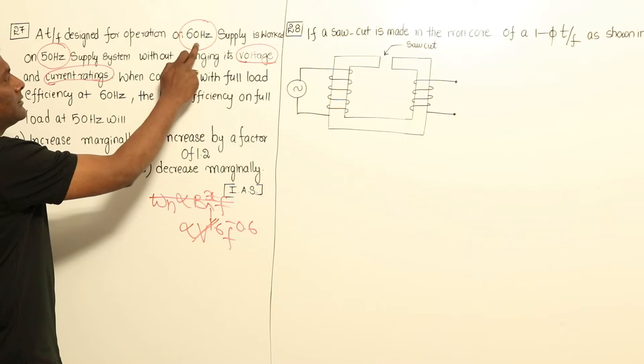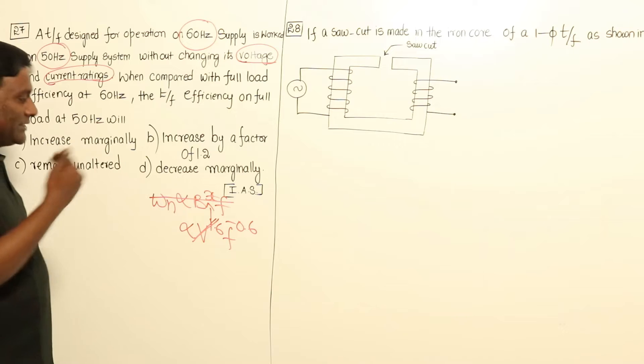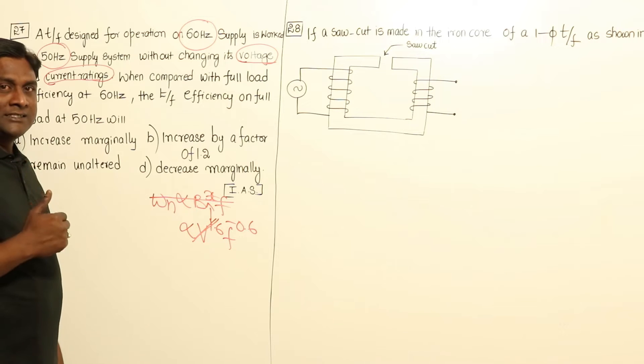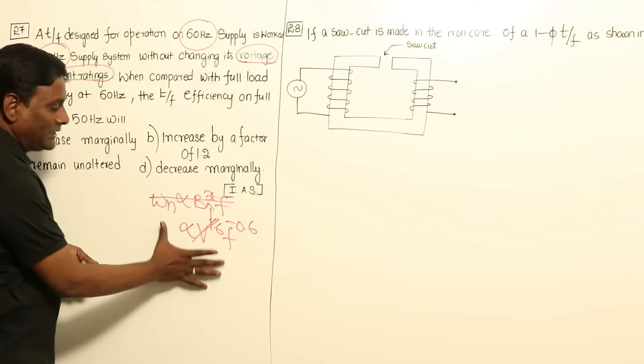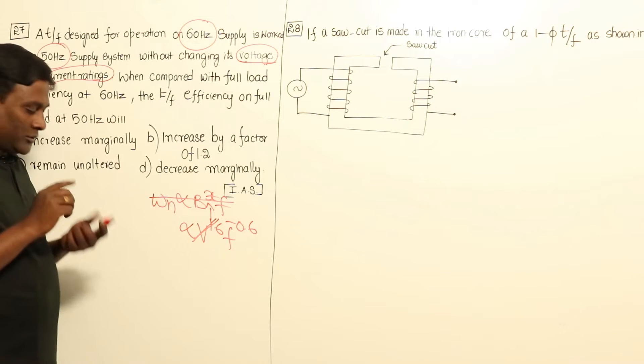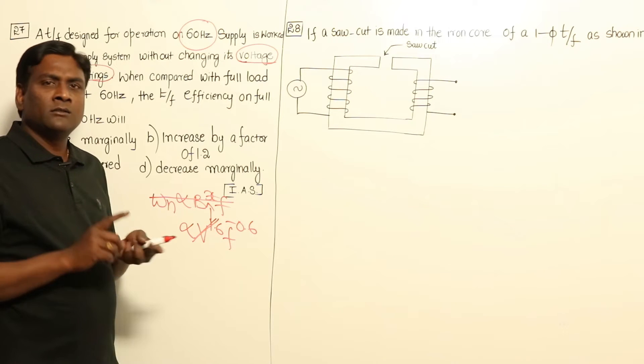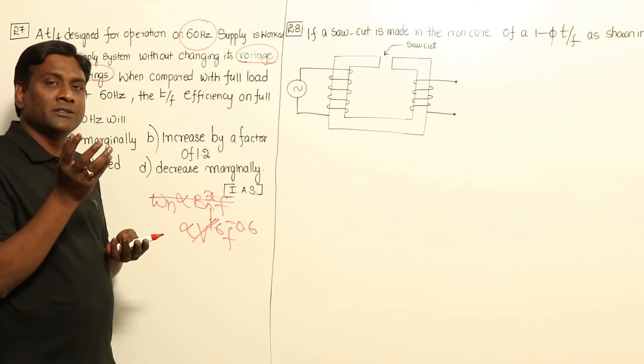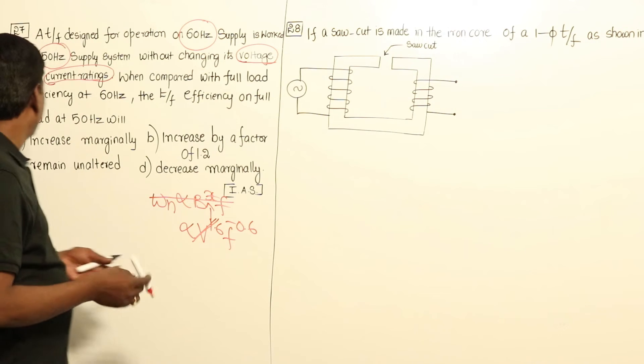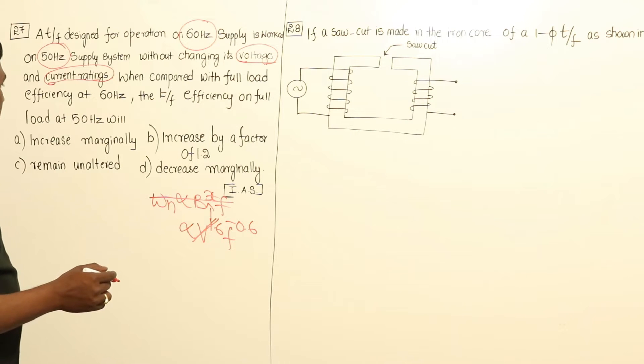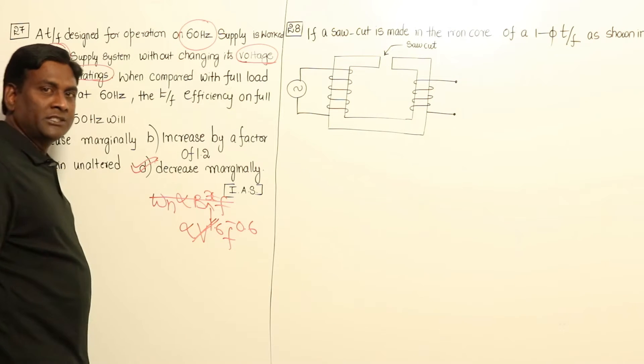The 60-hertz designed system is being operated at 50-hertz, meaning frequency is reduced. If frequency is reduced, hysteresis losses have to increase by this relation. So hysteresis losses increase, eddy current losses will be same, and copper loss also will be same. So total losses are going to increase, and therefore efficiency is going to reduce. The answer is 'decrease marginally' — efficiency has to reduce.